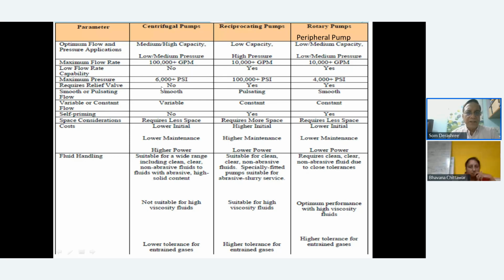Does it require a relief valve? No, it does not need one in a centrifugal pump, which you can run when shut off. It can continue to rotate till the liquid gets heated up. But with the reciprocating pump, no, it will burst the pipeline because it's reciprocating. And then you have variable and constant flow. Here, one piston stroke is one flow, so that is fixed. You cannot change that stroke length. Yes, you can change the RPM, of course, through VFDs and all that. But otherwise, by nature, unlike a centrifugal pump, it is not a variable flow.